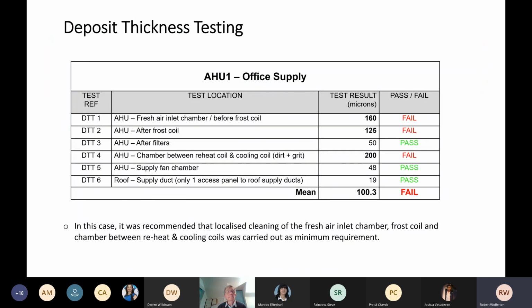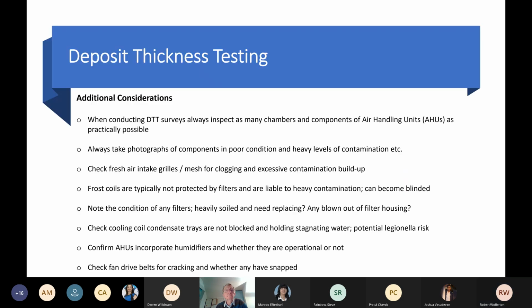And then we come on to a typical test that has been carried out. You can see we've carried out various dust deposit thickness tests here, with various readings across the system depending on where that is. You could either carry out localized cleaning or a full system clean to rectify the contamination within that duct and ultimately improve the air quality within the served area. So, additional considerations to dust deposit thickness tests and air hygiene surveys: you should always take photographs of the visual of the system. Visual inspection should really be the primary method of a building manager or an air hygiene compliance company coming in and checking the system for contamination.